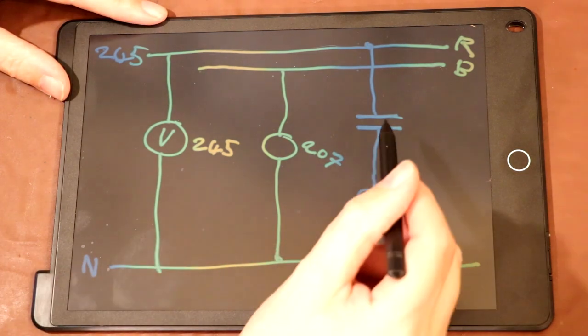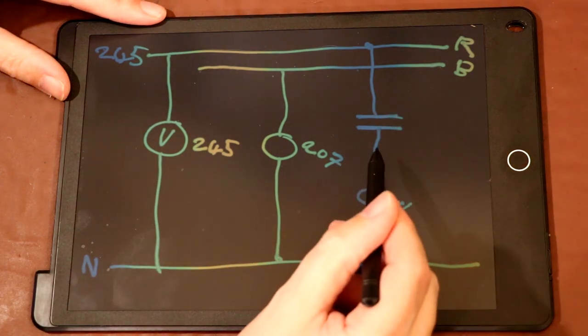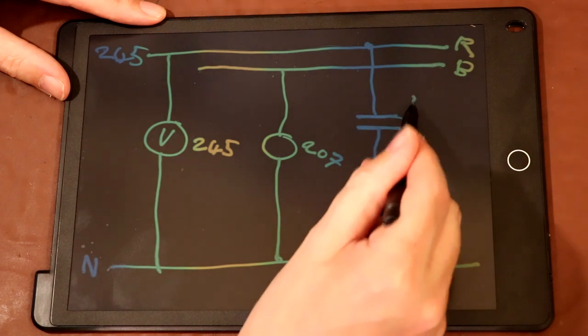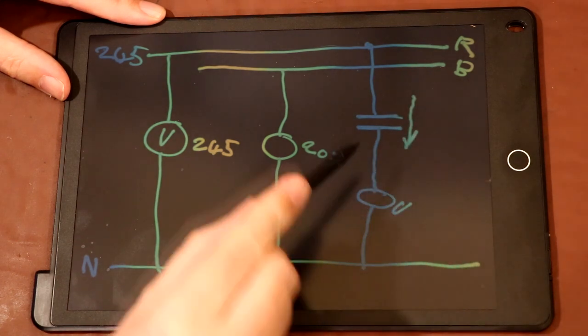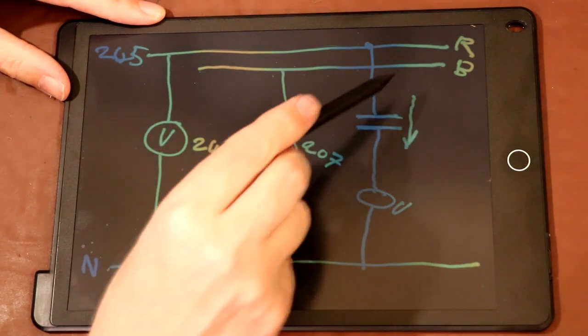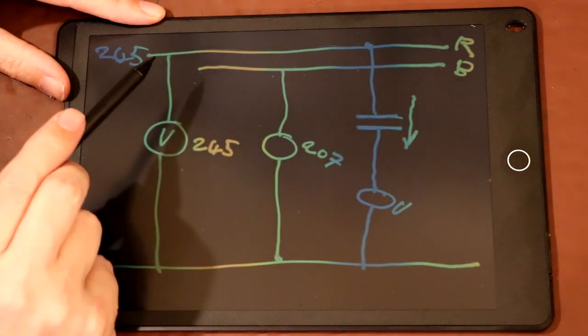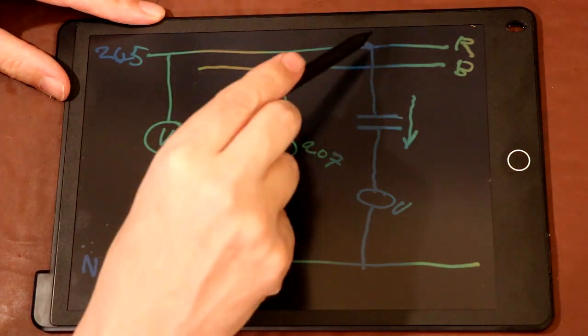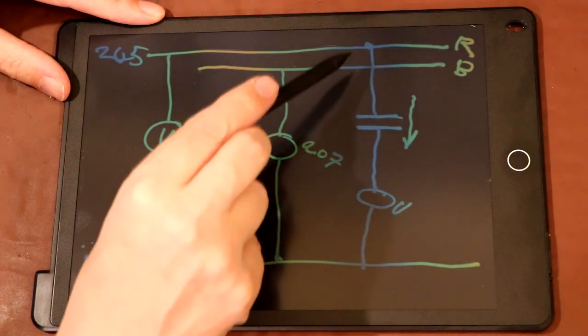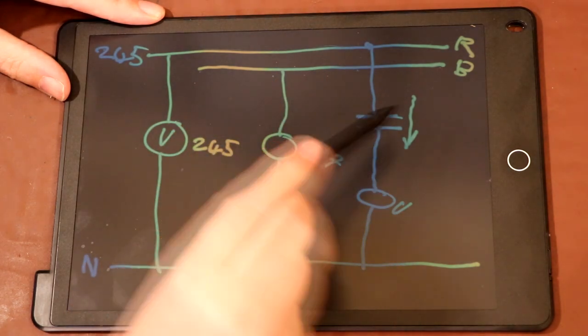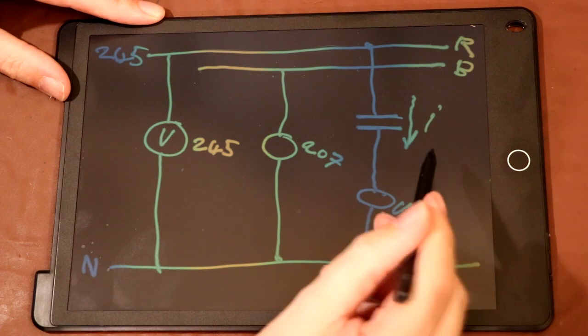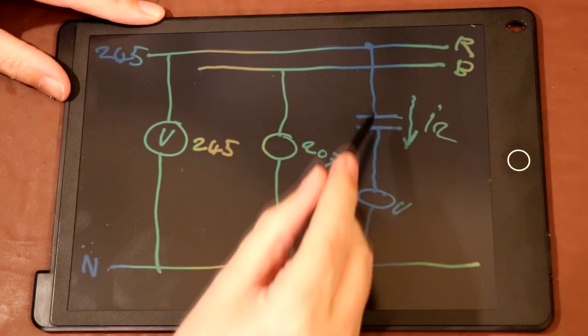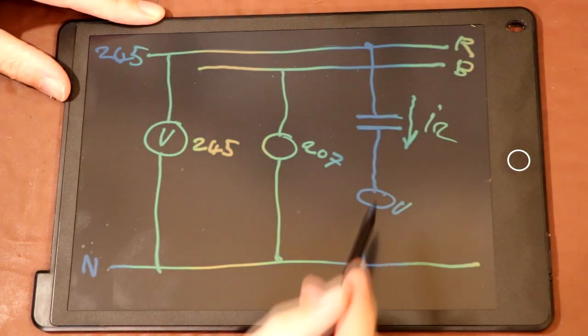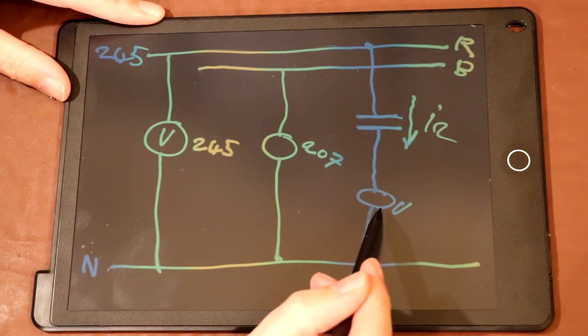Now, of course, we know that DC can't flow through a capacitor, but AC can, so we're getting an AC current now, which is actually flowing through our circuit. Even though the black wire isn't connected to anything, the fact that the two red and the black conductors are separated by this insulator means we form this capacitor, that's going to allow some AC current to actually flow through our circuit here into our voltmeter, and that's why we're getting a reading on the voltmeter.